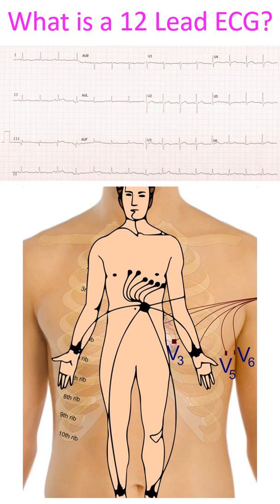The chest leads are theoretically unipolar recordings with all three limb electrodes contributing to the central terminal. They are named V1 to V6 or C1 to C6. V1 is placed in the fourth right intercostal space close to the sternum and V2 on the corresponding location on the left of the sternum. V4 is in the fourth left intercostal space in the mid-clavicular line, while V3 is positioned midway between V2 and V4. V5 and V6 are positioned at the same horizontal level as V4 in the anterior axillary line and midaxillary line respectively.